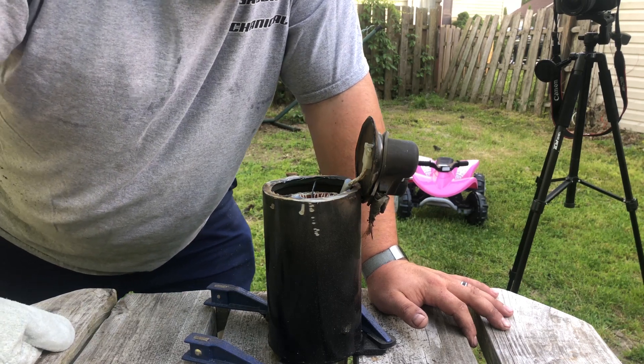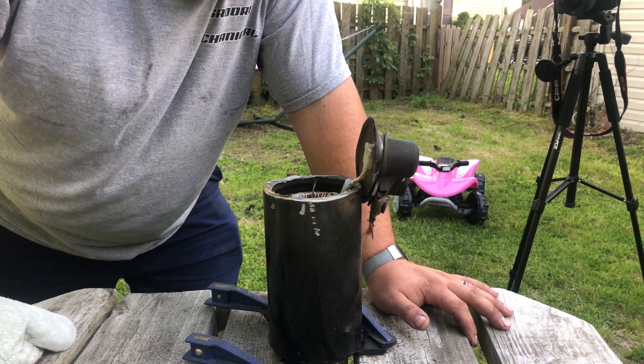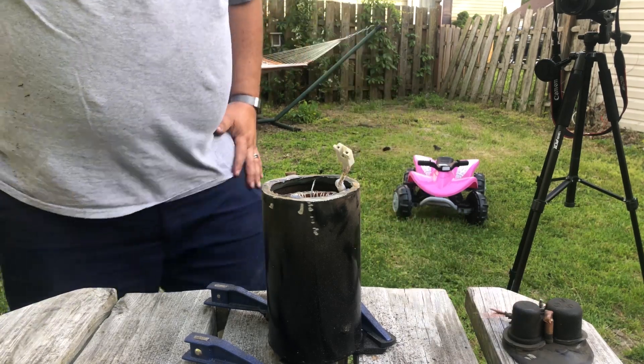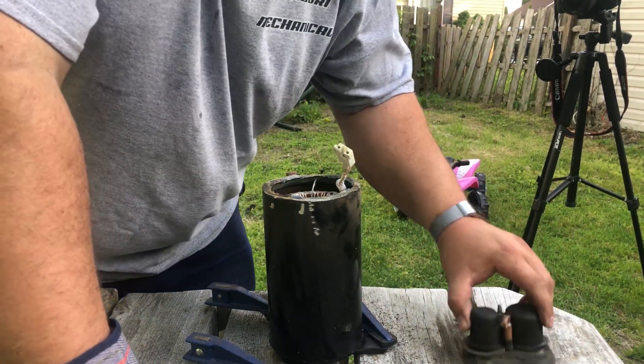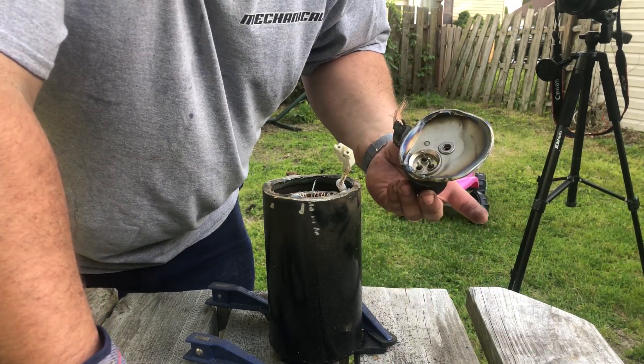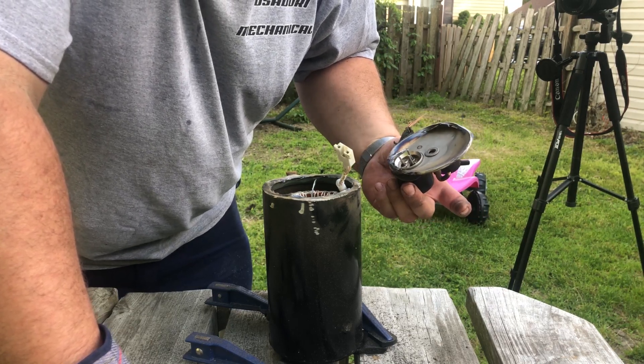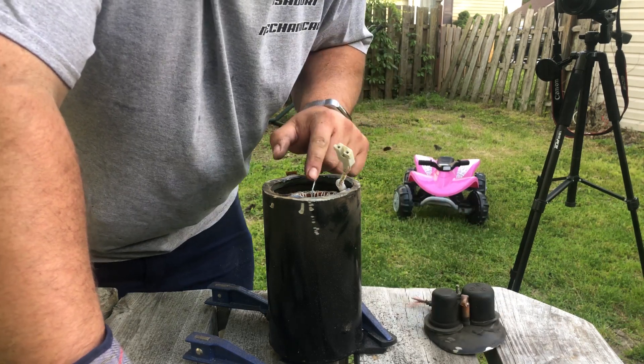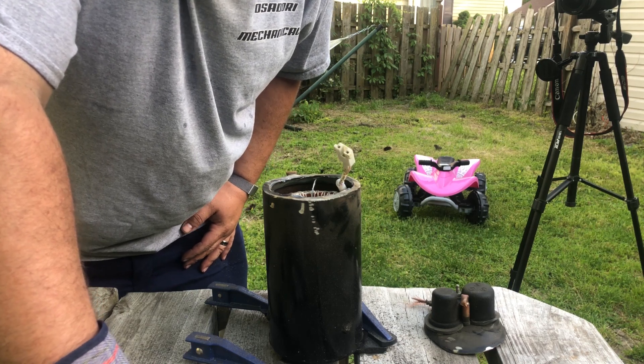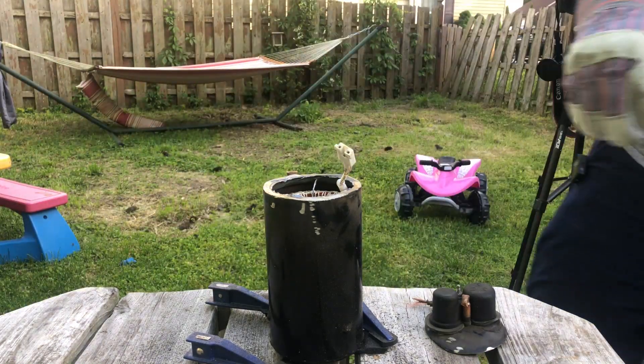It is definitely not what I was expecting. I think I have to grind this edge down a little bit further. So I'm going to show you guys what I found. In case you're interested, this is the discharge port - this right here is the discharge and it just blanks right there.